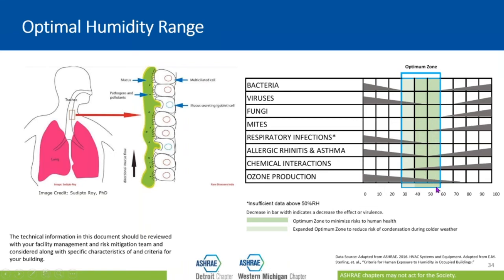So this graph here comes straight from ASHRAE, and we can see here this ideal range of 40 to 60% relative humidity. Now in Michigan, we do suggest that folks expand that range down to 30%, particularly in places that may not be able to handle higher relative humidity levels. A lot of buildings are older, they may have single pane windows, they may have a lot of woodwork if they're old houses of worship, and the 40% in the wintertime may not be achievable. And so if we can at least get to 30, that's something.